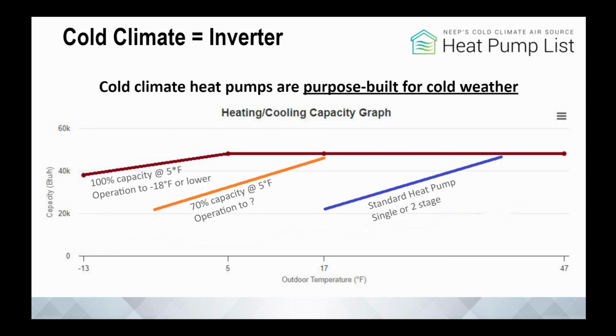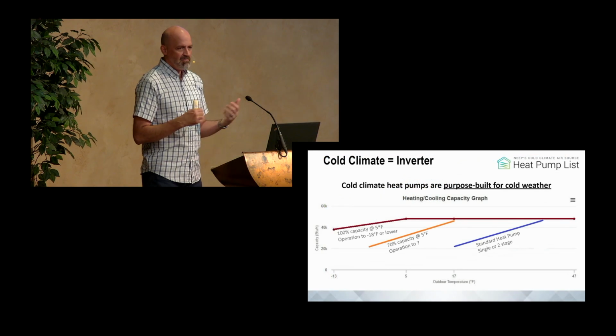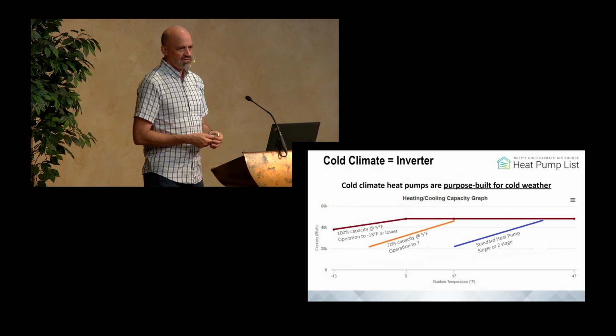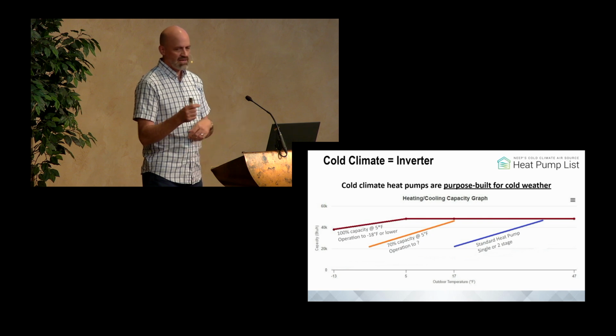That red line across the top and down the very left side, that's really the true cold climate heat pump—100% capable at 5 degrees or thereabouts. It does taper off, but it holds its capability at or near our design temperature of about 0 degrees in the Front Range, whether it's 1 degree, 5 degrees, or -1, similar numbers.